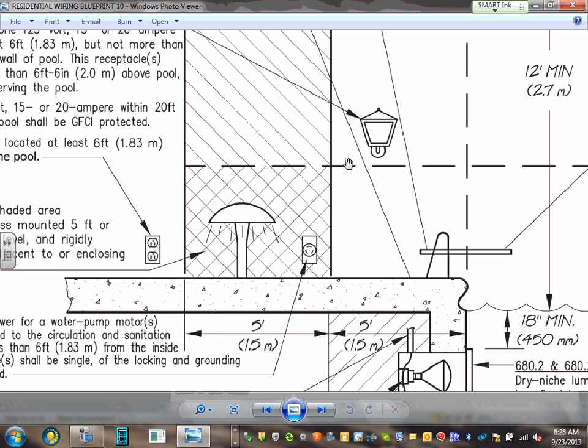Summarize. For swimming pools, receptacles shall not be closer than 6 feet. They have to be GFCI between 6 and 20. Lights, typically 12 feet. You lower them to 7.5 and GFCI them. They have to be listed for that location. Lights, typically low voltage contact limit, they call them, are fed by an isolating transformer, wet niche or dry niche, with an equipment ground conductor number 12. Everything in the swimming pool has to be bonded. Everything metallic within 5 feet of the swimming pool, to a height of 12 feet, has to be bonded with number 8 solid copper.